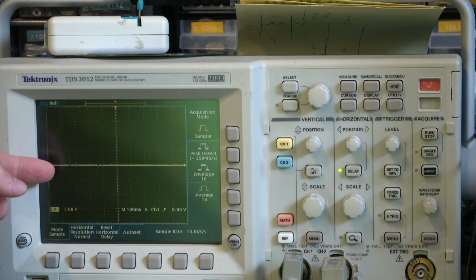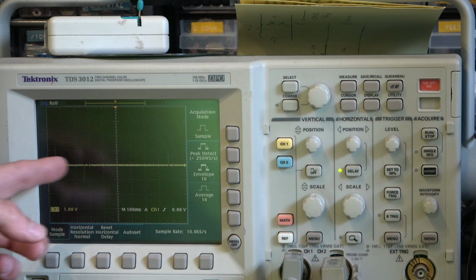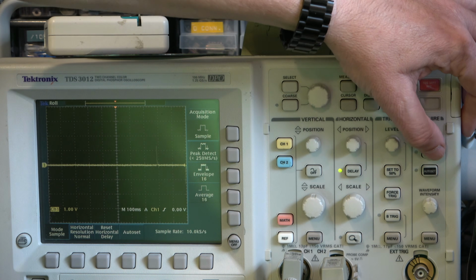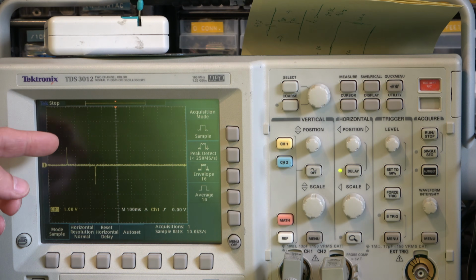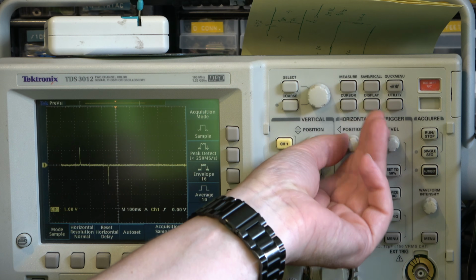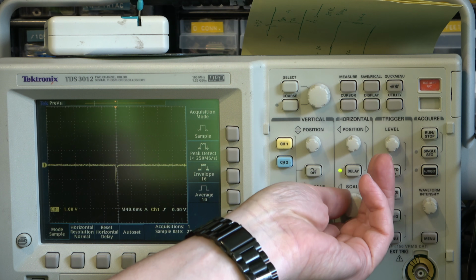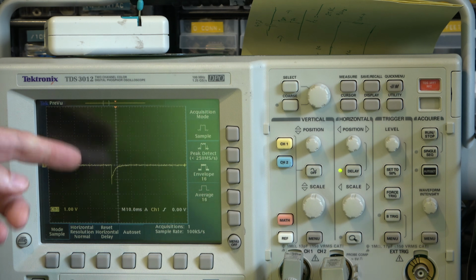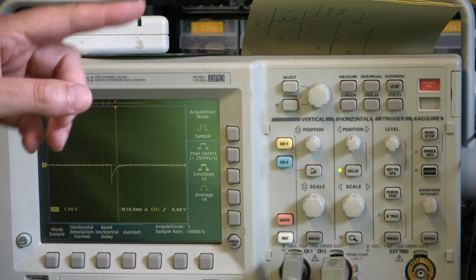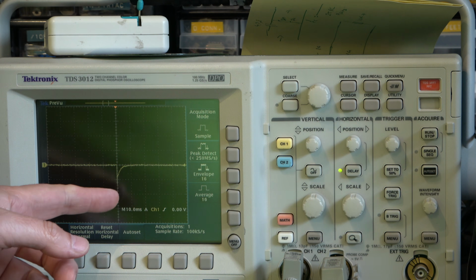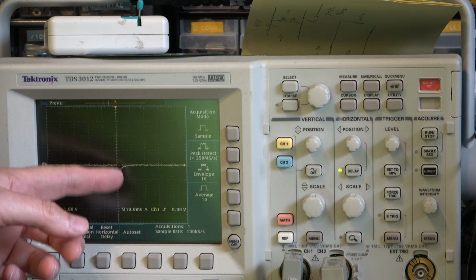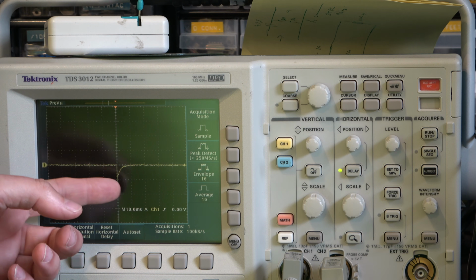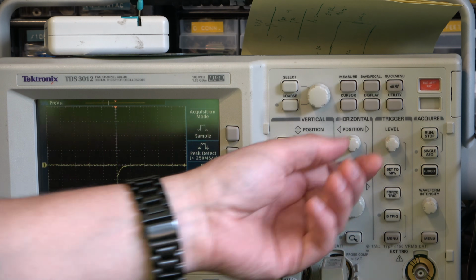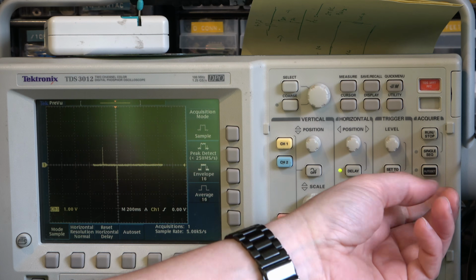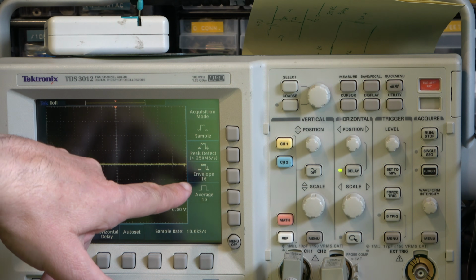So I think you can see these negative and positive going pulses going past. If we set to single sweep, we'll capture a set, and then what I can do is zoom in to the data and get to view data that's in an event that's already gone. So you can see the fairly short pulse there where we've got 10 milliseconds per division. We've got a pulse of about 1 or 2 volts that fades away in about 5 milliseconds, which is happening only very infrequently in a waveform of several seconds.